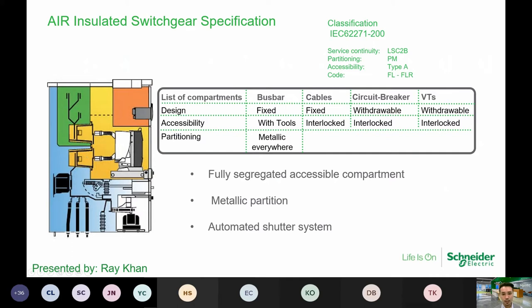Also, just to share some of the designs that we see, sometimes there's a mixture of specs where, for a gas insulated design, they put in the statement of automatic shutters, which is not appropriate, all right, because automatic shutters are a feature designed for air insulated switchgear. Apart from this, we talk about the service continuity for the switchgear, which is LSC2B, all right. These are certain requirements in the IEC 62271-200 itself. It is a test procedure, all right. In this test procedure, we also talk about partitioning. The partitioning for PM actually refers to metallic partitions, all right.